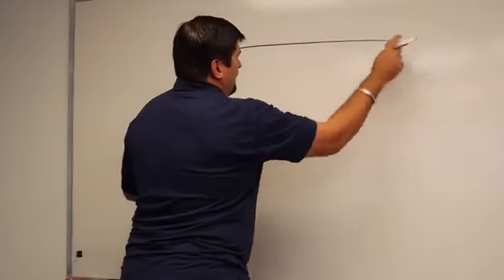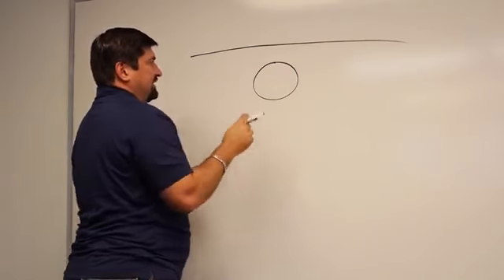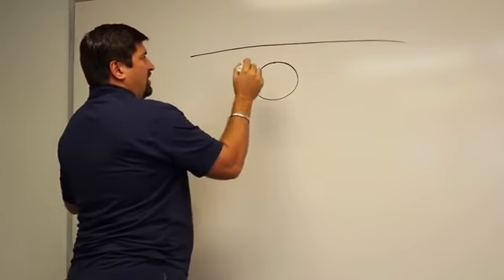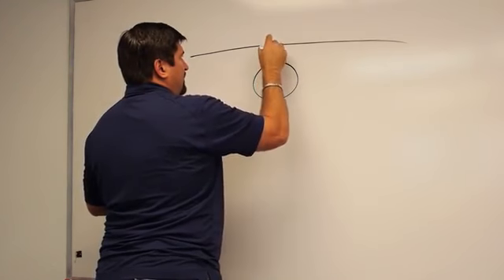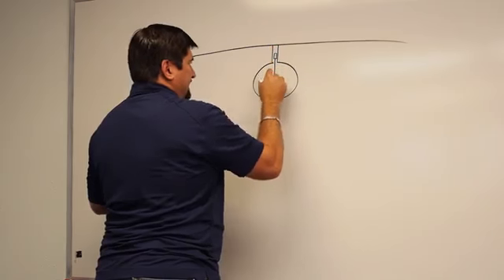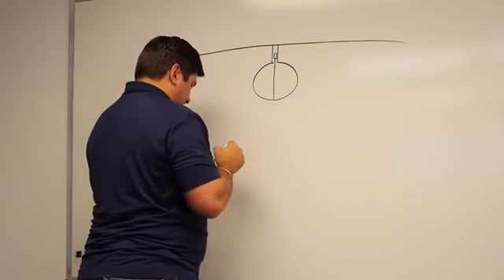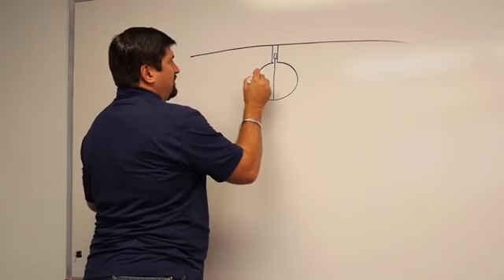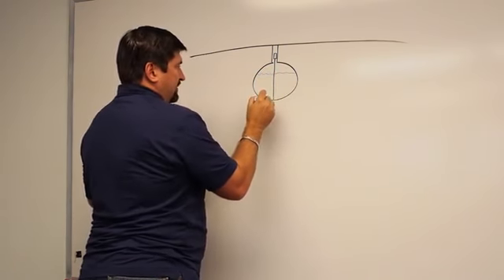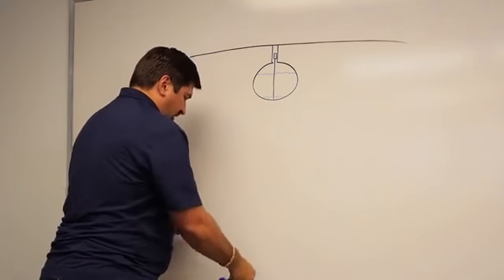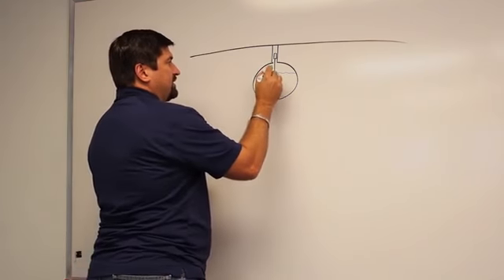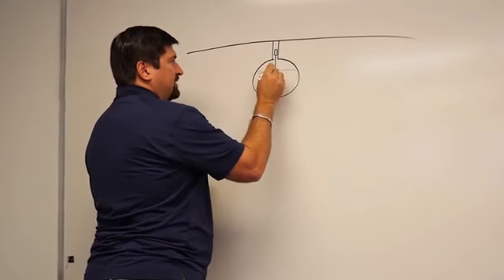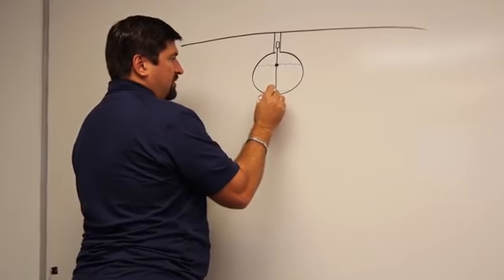So when we start looking at, we understand the why, now we want to give you a little bit about how. How does an ATG work? If I look at the same mock-up that I had before, where everything's underground, and I've got my tank looking at it from the other direction, basically I'm going to install a probe in this tank that sits on the bottom, and what you'll see is the fuel level inside this tank and the water level inside the tank. And on this probe, we put a float that will float on the product and something that will float on water.